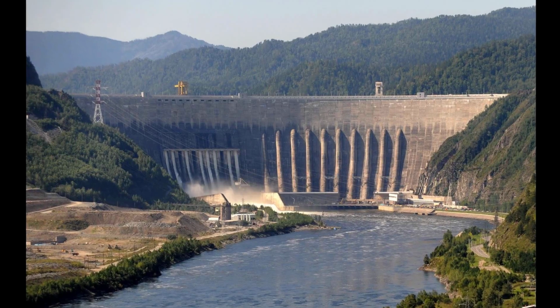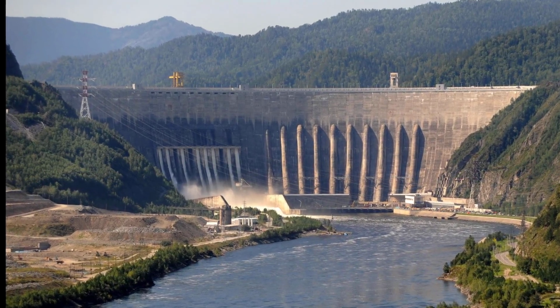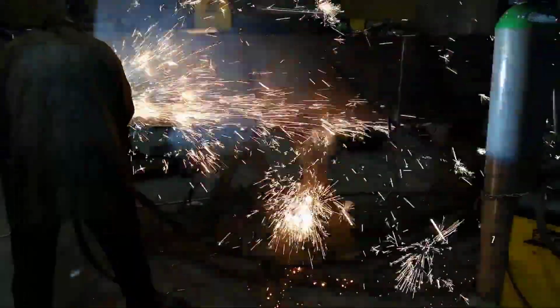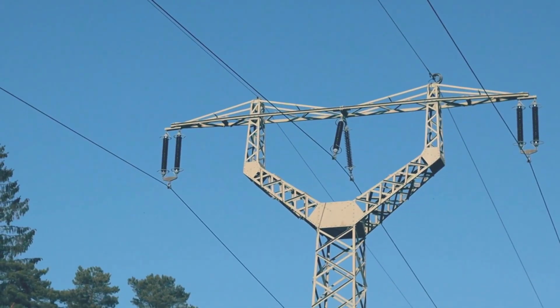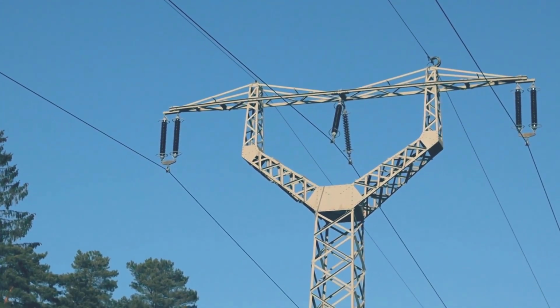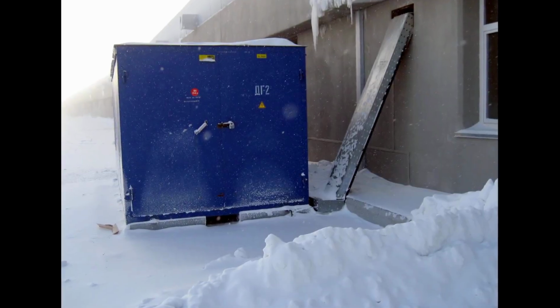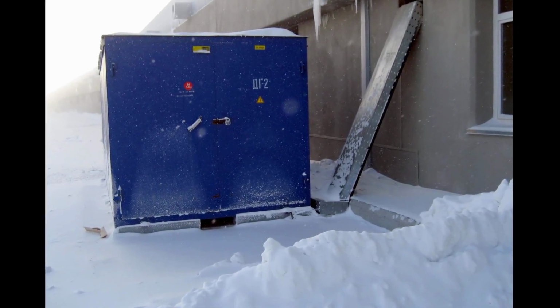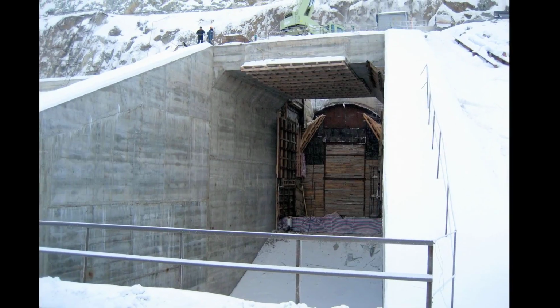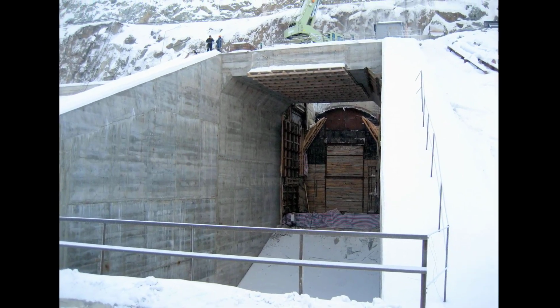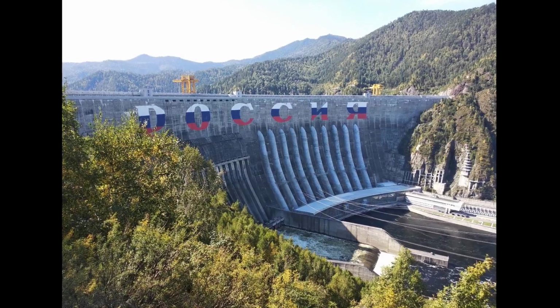The station went from 4,400 megawatts to nothing, which created the problem that could have turned a disaster into a catastrophe. The gates that shut off water to the turbines are closed by the station's own power, and the station no longer had any. The reservoir was now draining, uncontrolled, through a hole in a building at the base of a 245-meter dam. The only way to stop it was to close 10 intake gates by hand.